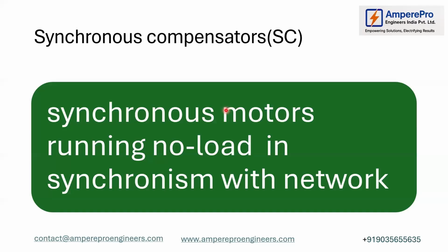The second one is synchronous motors, which run at no load and stay in synchronism with the network. When you run that motor at no load, it gives the reactive power support which is needed by the grid. It will be added to the grid. So this is one side of these things.